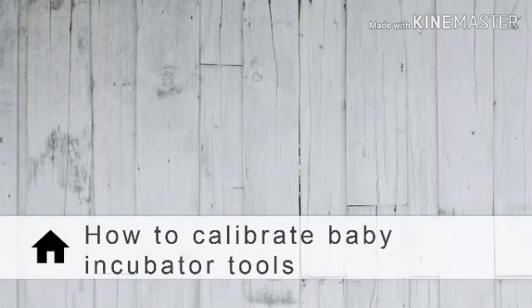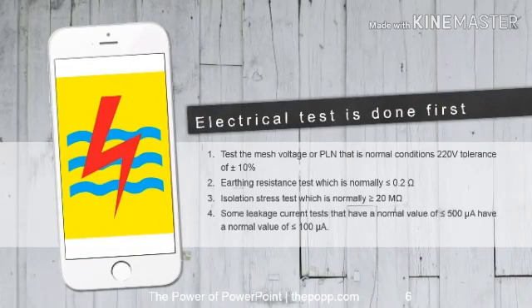How to calibrate baby incubator tools. Before calibrating this tool, electrical tests are performed first. One, test the mains voltage or PLN, which is normally 220 volts with a tolerance of plus or minus 10%. Two, earthing resistance test, which is normally less than 0.2 ohm. Three, isolation resistance test, which is normally more than 20 megohms. And then four, leakage current tests, which have a normal value of less than 500, and less than 100.